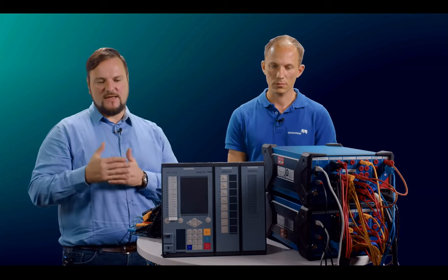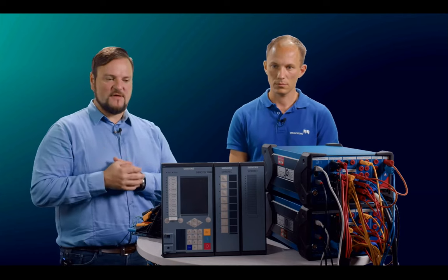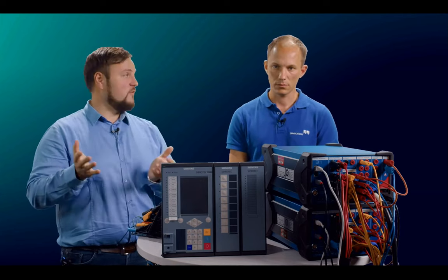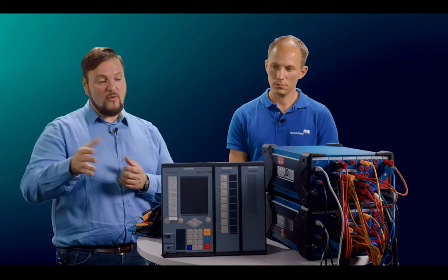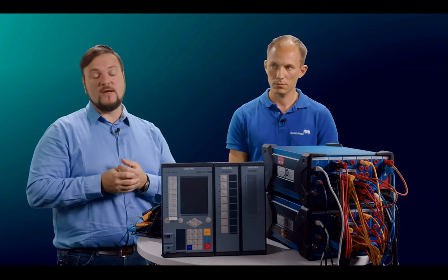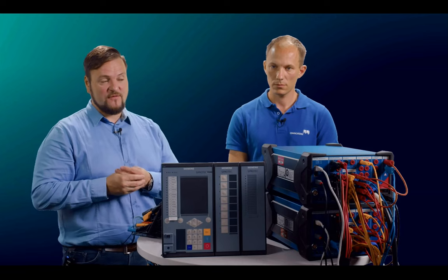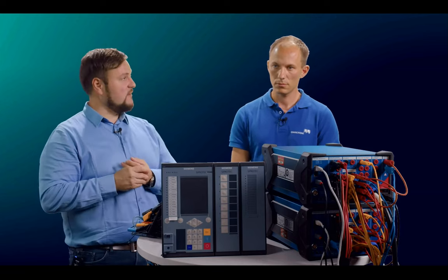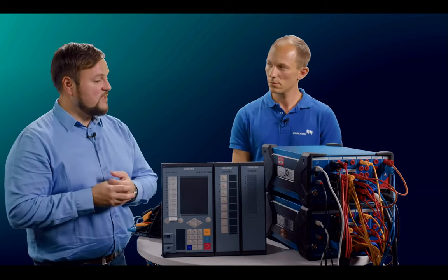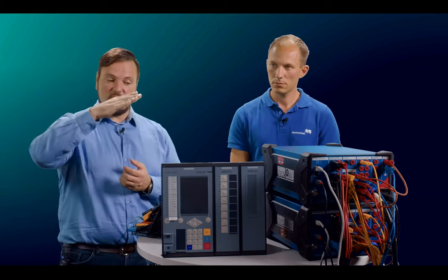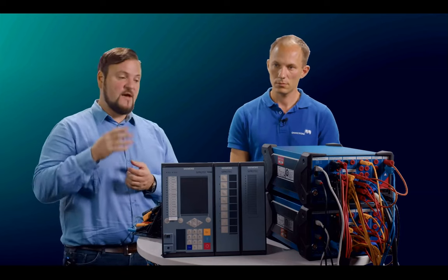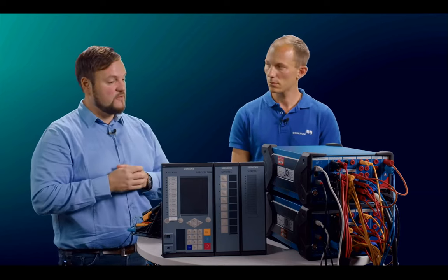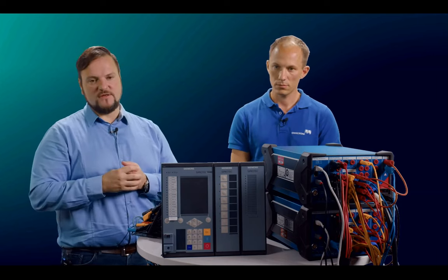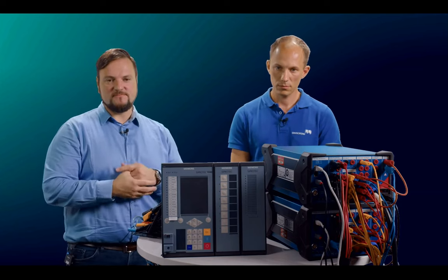I can't give any time. The time is dependent on the voltage and also on the frequency on the motor bus, in the end on how much inertia we have. That means if we have bigger motors on the motor bus in the simulation, we will see that the voltage is decreasing slower. If we have only fewer or small motors, the voltage is decreasing faster. Next question.